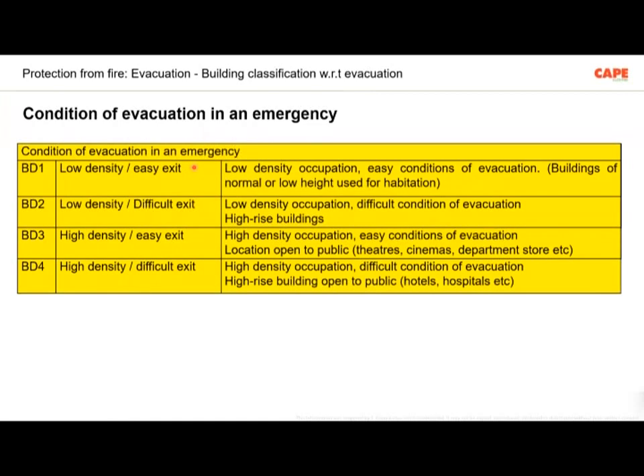There are 4 categories recommended in the electrical engineering standards by IEC 60364, followed worldwide, be it Europe or America. These classifications are called BD1 to BD4. BD1 stands for low density, easy exit, and BD4 stands for high density, difficult exit. One of the conditions we need to understand is that this classification shall be done by the authority involved with fire, for example the fire and safety department. Basically, they set that a building more than 15 meters in height with more than this many people comes under the BD2 category. Then they say, for example, a hospital of 10 floors comes under the BD4 category.